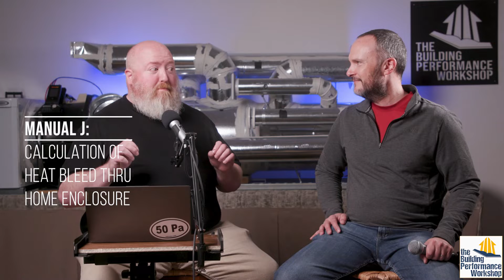Understood. But the key word here is estimated, right? And estimated is another word for ballpark, made up, rule of thumb, whatever. It's not necessarily going to be what my target airflow is, because one of the more annoying things I'm fond of saying is Manual J does not tell you what equipment you need. Manual J doesn't tell you anything about the equipment, it tells you about the building. It tells you how much heat you gain, how much heat you lose, how much moisture you gain. That's all it does. Then your job is to go find a piece of equipment that will make that happen.